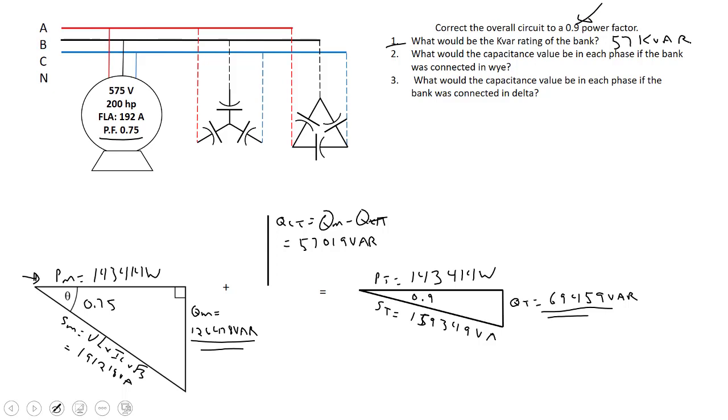Now moving on to questions two and three, we're going to have to figure out the VARs per phase. The VARs per phase, QC total is the same as saying QC of each phase times three. So if I want to know the QC of each phase, I'm just going to take my QC total and divide that by three. QC of the phase works out to about 19,006 VAR.